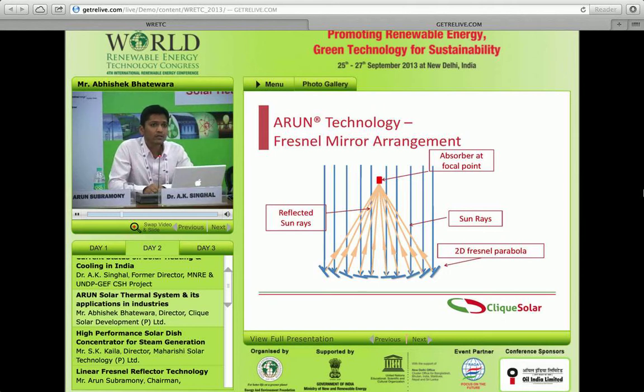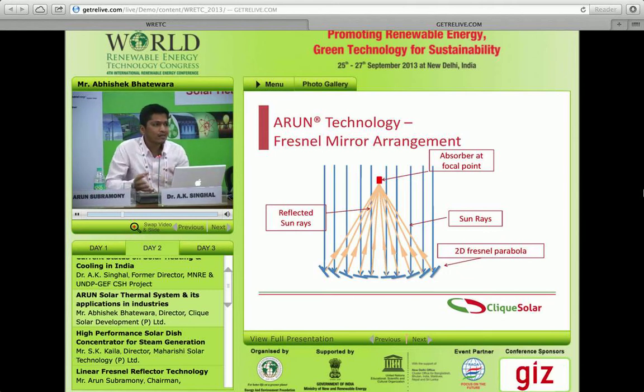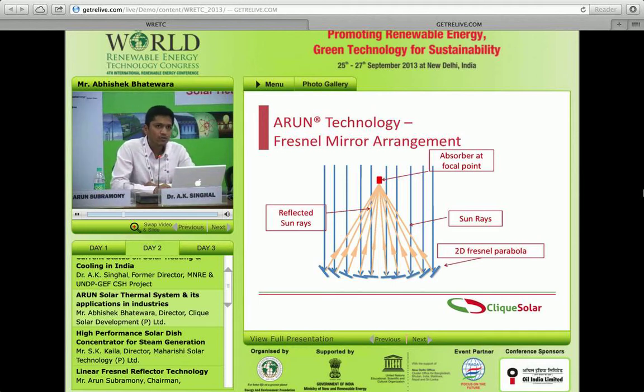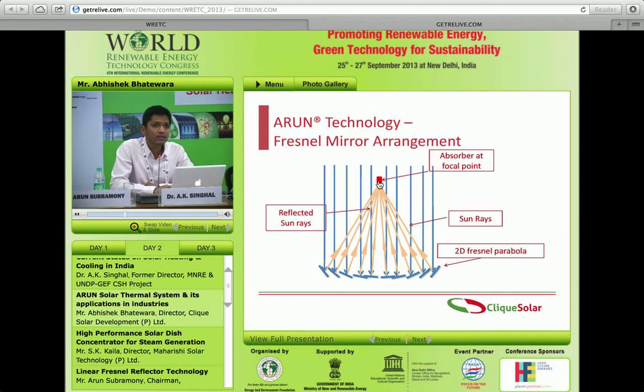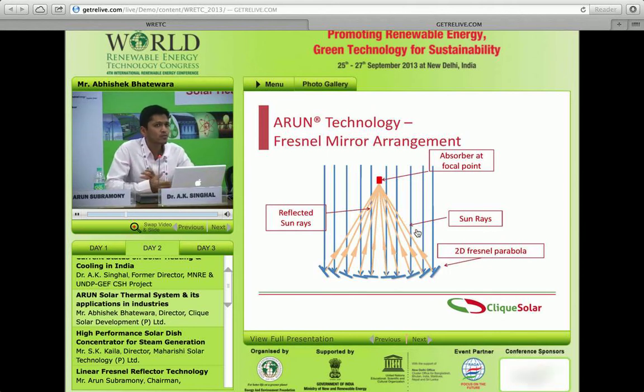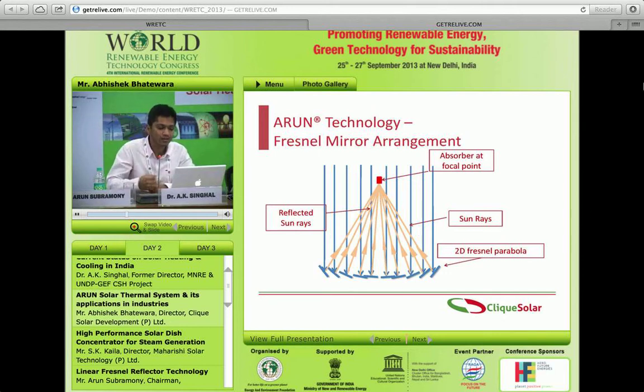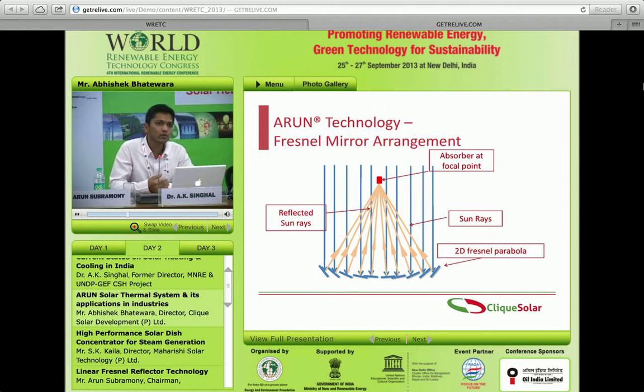When sun rays are incident on this arrangement, they all get concentrated at one particular point. To use this energy, you pass water through that point — when water passes through, it gets heated. By controlling the flow rate, you decide the temperature you want. For higher temperatures, you reduce the speed so water spends more time at the concentrated point. The output could be high-pressure steam, pressurized hot water, or thermic oil going up to 300 degrees Celsius.